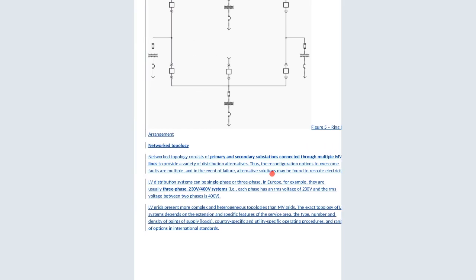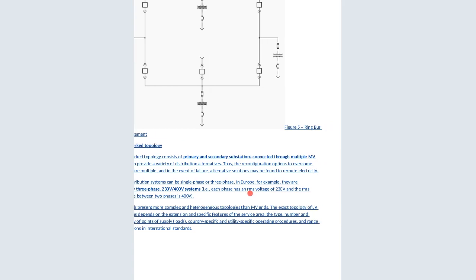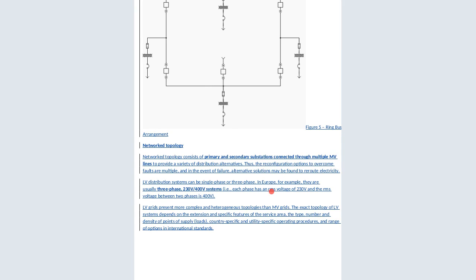The network topology consists of the primary and secondary substations connected through multiple MV lines to provide a variety of distribution alternatives. Thus, the configuration options to overcome failures are multiple, and in the event of failure, alternative solutions may be found to reroute electricity.